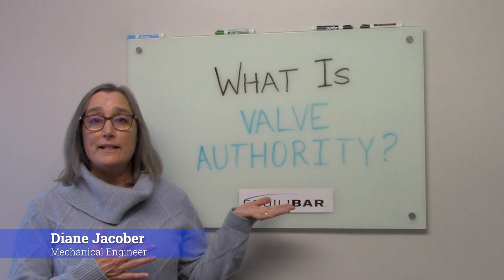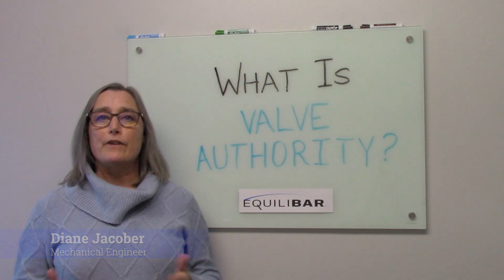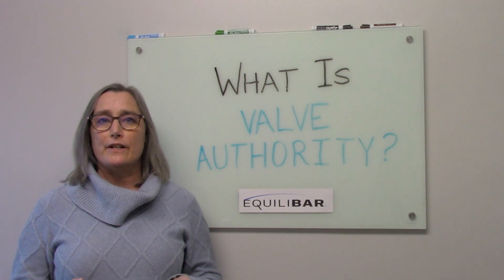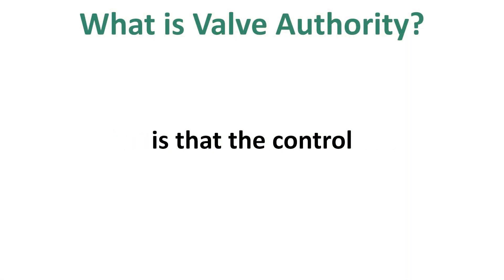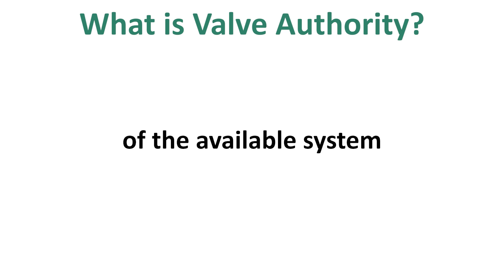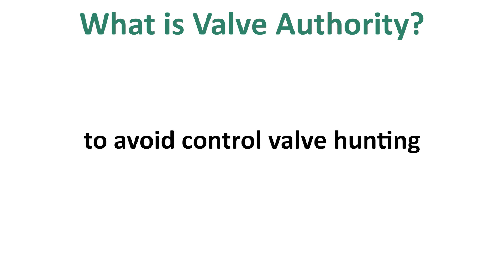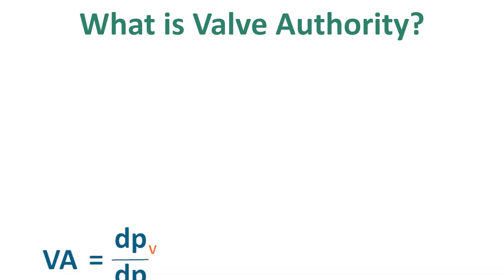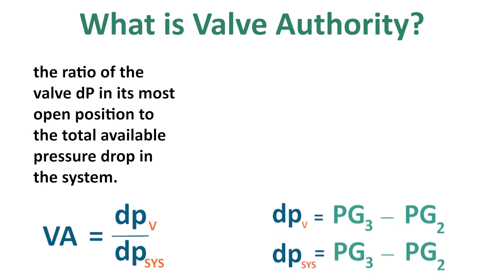What is valve authority? Engineers who size control valves use the term valve authority to avoid selecting a valve that's too large for the application. A common rule of thumb is that the control valve needs to consume at least 25 percent of the available system pressure drop in its most open position to avoid control valve hunting. Valve authority is the ratio of the valve DP in its most open position to the total available pressure drop in the system.